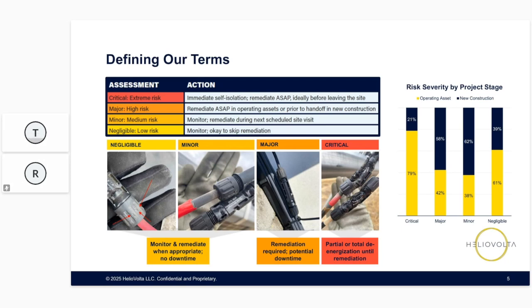When we get into the critical issue, there's an under-torqued back nut on the field-made home run that is catastrophically damaged. You can see that it is charred and melting. Additionally, there were under-torqued back nuts systemic on this site. There were multiple instances of overheating connectors. So the catastrophic failure event has already happened. There are more that are possible, and they are imminently possible. So it's time to shut down.